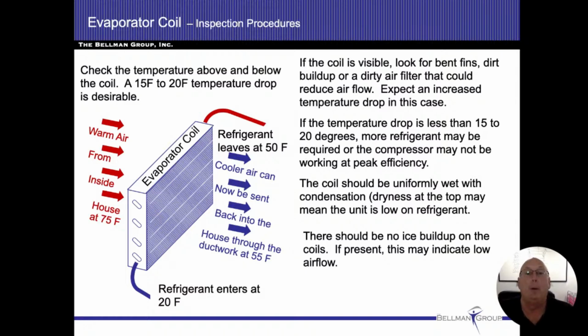All right. I want you to remember that 15 to 20 degree temperature drop. So if it comes in at 70, it should be leaving somewhere around 55 to 60 degrees, 15 to 20 degrees difference. If you can see the coil, we're going to be looking for damaged fins, bent fins, damaged tubing. You're going to look for brown or black stains. Sometimes they'll look like efflorescent stains as well on there. Those are going to be showing refrigerant leaks in the past.